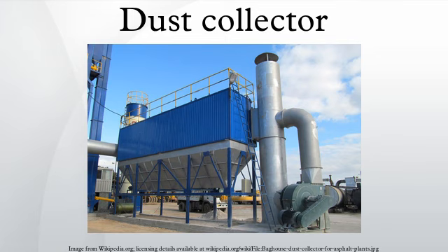The most common types of centrifugal, or inertial, collectors in use today are single cyclone separators. They create a dual vortex to separate coarse from fine dust. The main vortex spirals downward and carries most of the coarser dust particles. The inner vortex, created near the bottom of the cyclone, spirals upward and carries finer dust particles.